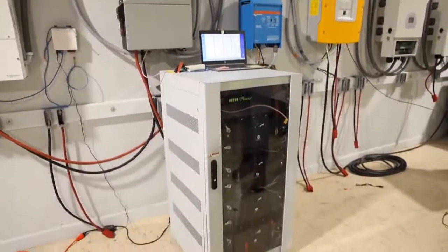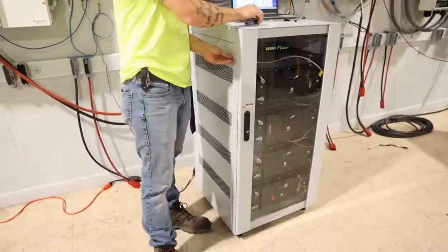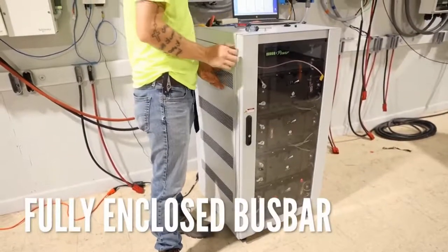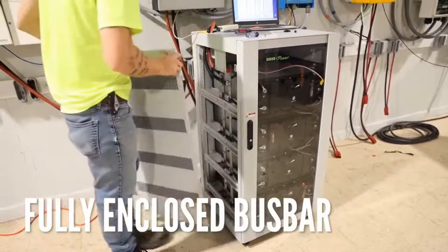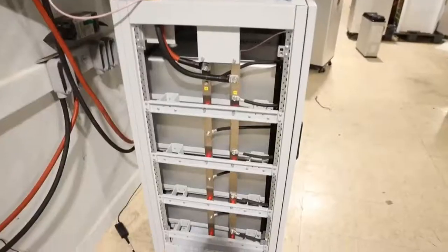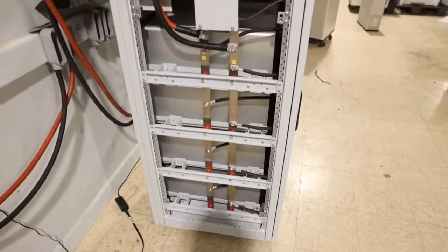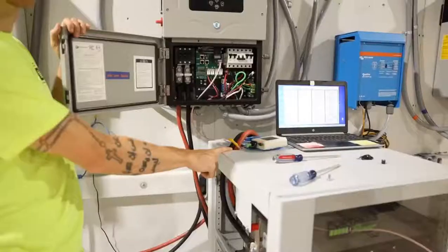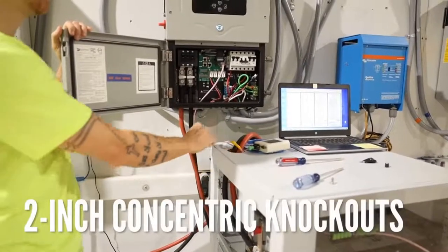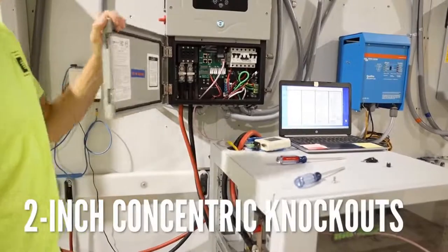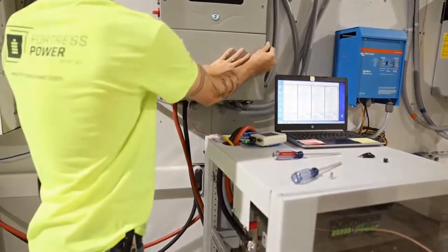The Flex Rack is wider than a typical server rack, allowing for a fully enclosed bus bar. The left side of the Flex Rack is removed during installation to access the bus bar. The bus bar connects to the inverter cables through 2-inch concentric knockouts, and installers can create additional knockouts with a hydraulic punch.